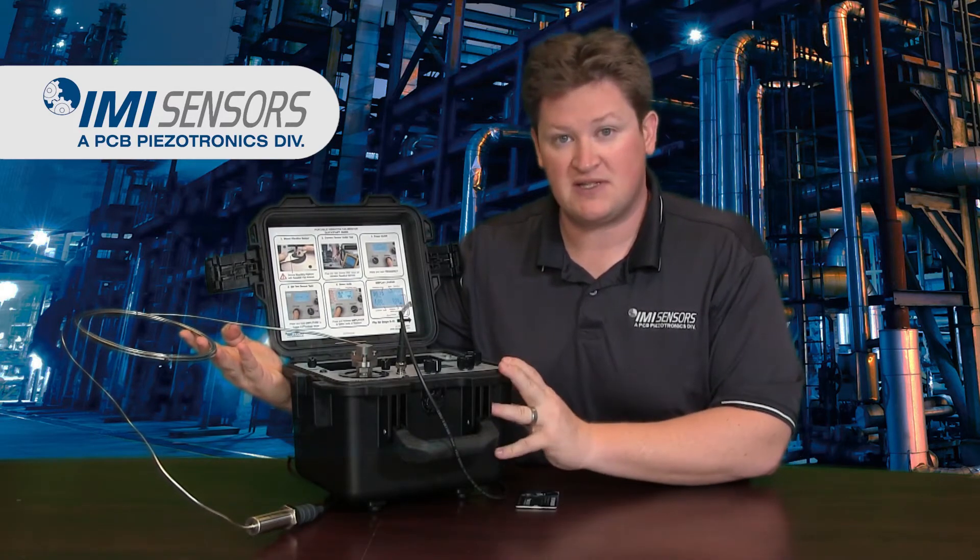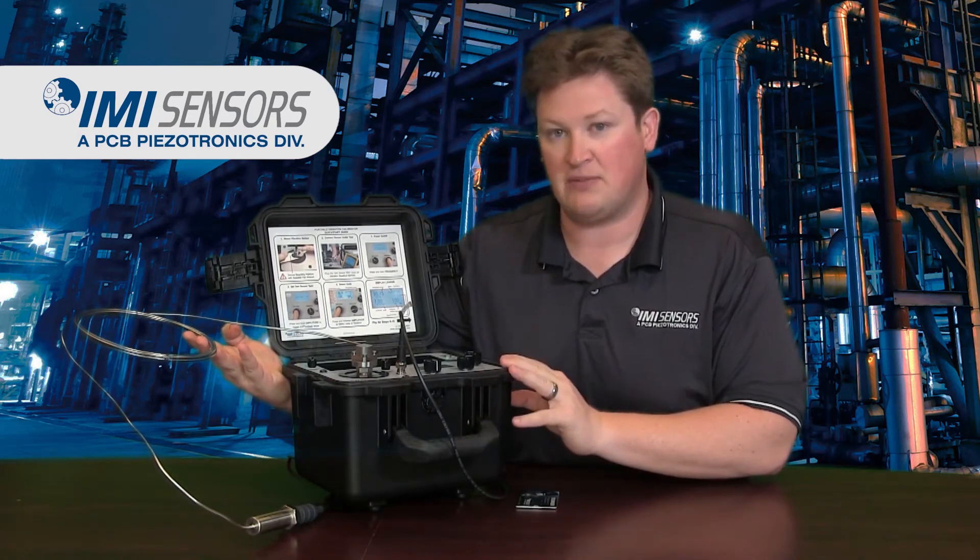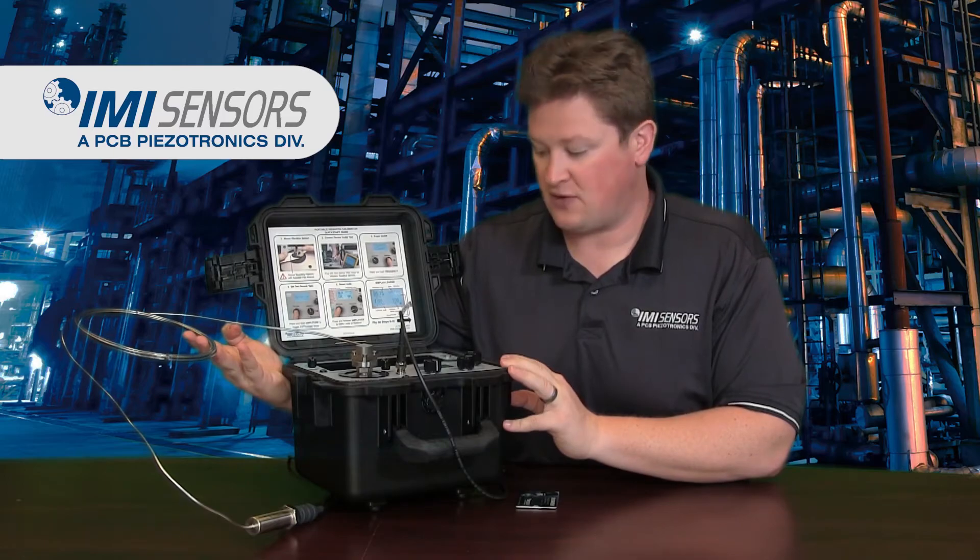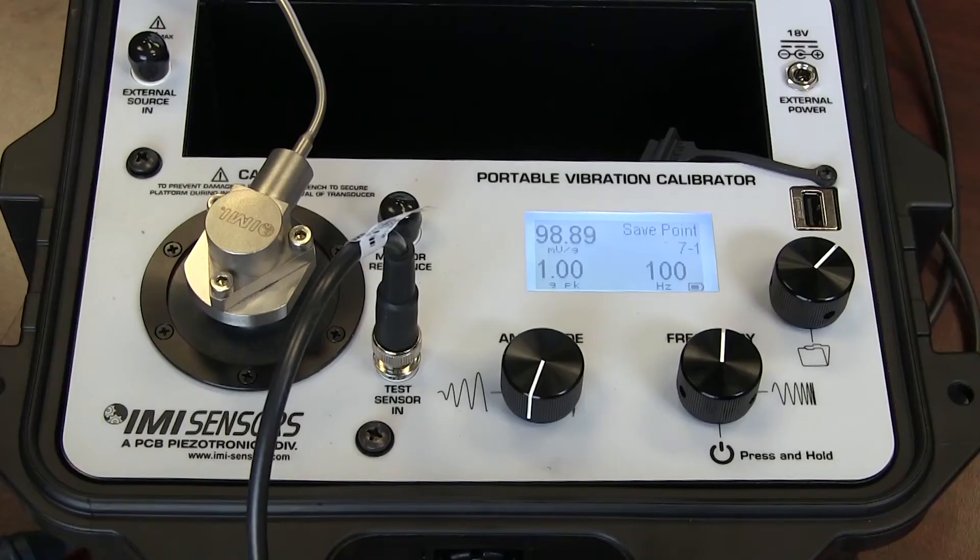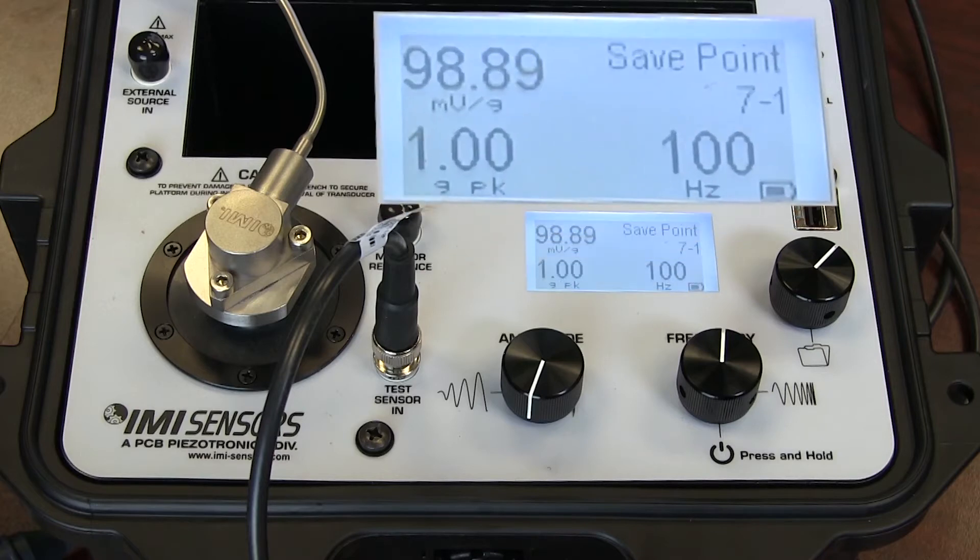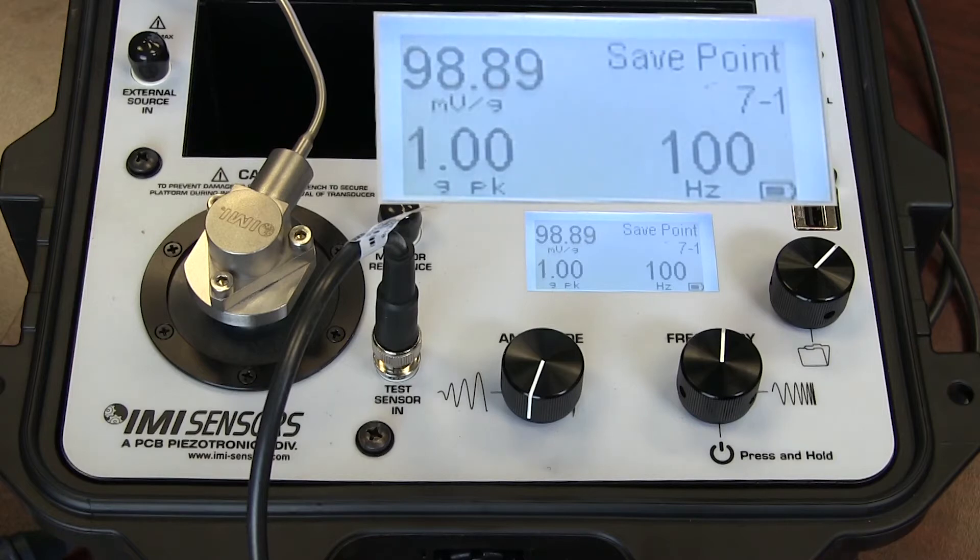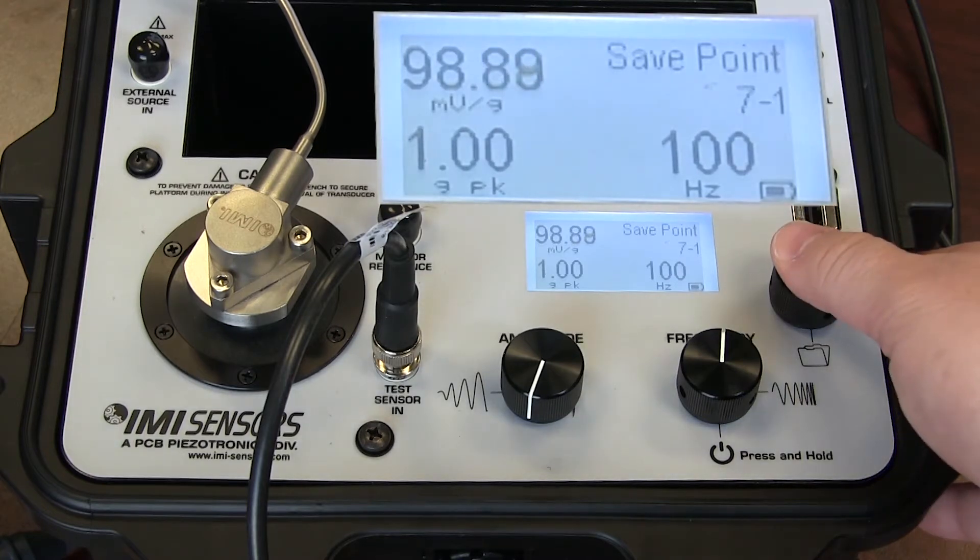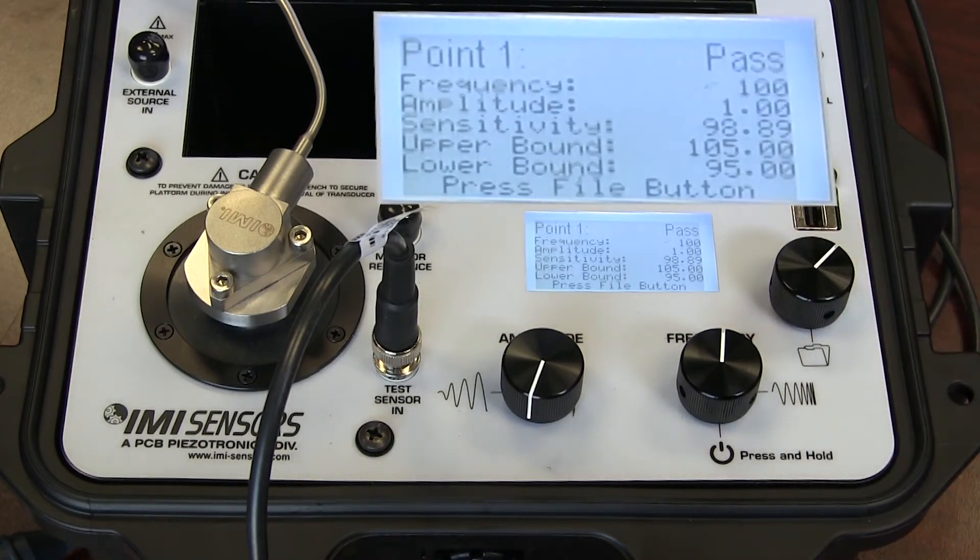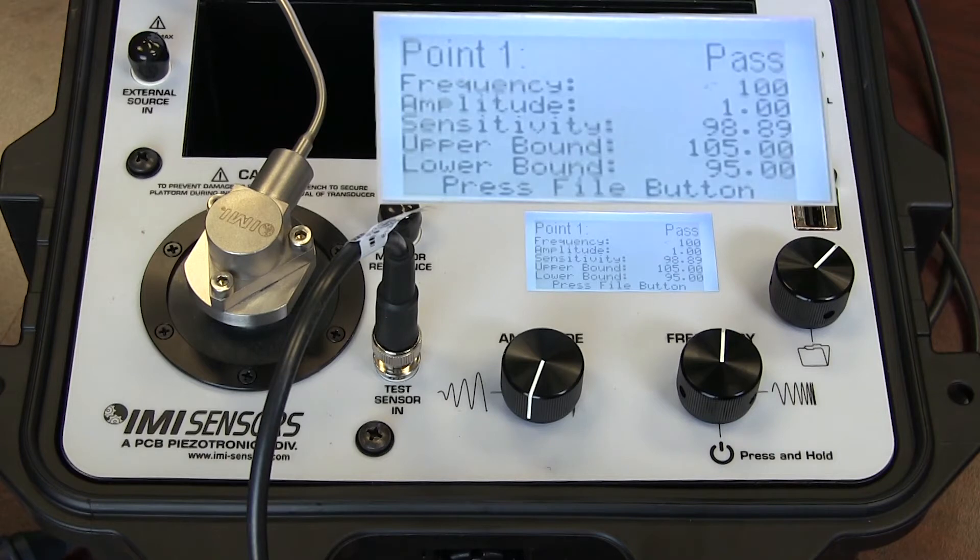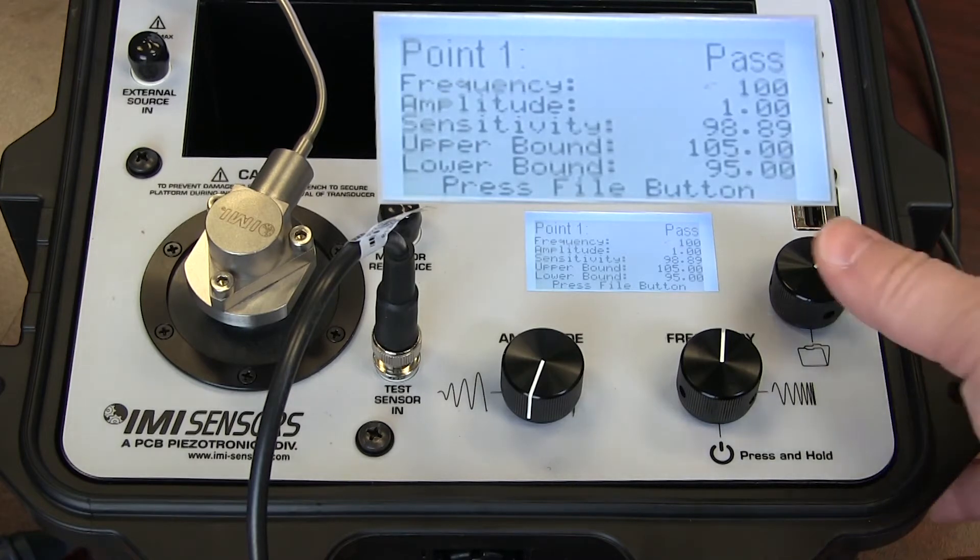But let's get on with it. Let's test this accelerometer using an automated test that I've already programmed into the shaker table. So our first test point is operating right now at 100 Hz and 1G peak. And you can see that my output is 98 mV per G, 99 mV per G. Desired is 100, plus or minus 5% tolerance. So this sensor passes. You can see the next screen here tells you that the sensor passes calibration because its output is 98.89 mV per G, which falls between the upper and lower bound of 105 to 95 mV per G. And we tested it at 100 Hz and 1G peak.